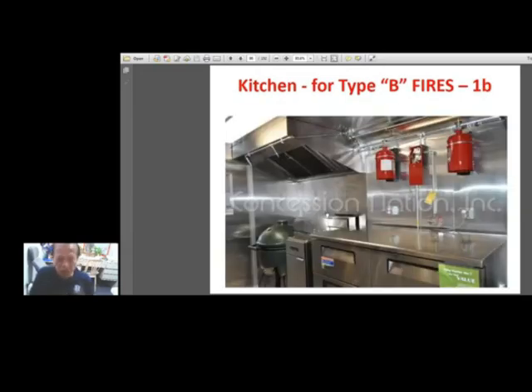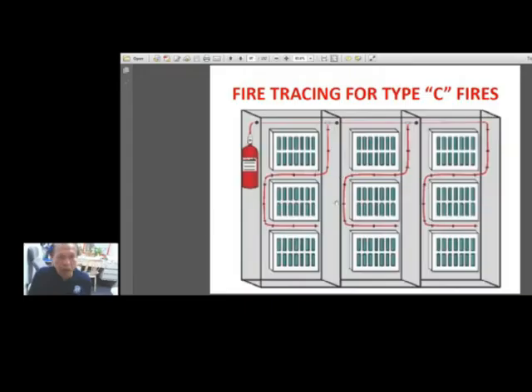And another kitchen showing the agents. And these tanks here are the agents. And in electrical, usually switch gears, control panels, and switch gears, electrical switchboards can be provided with the necessary piping to the different components, so that the moment you detect fire, this gas would be spewed in the area and would put off the fire very fast.